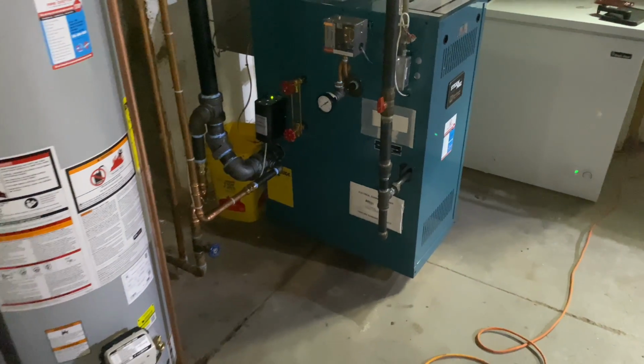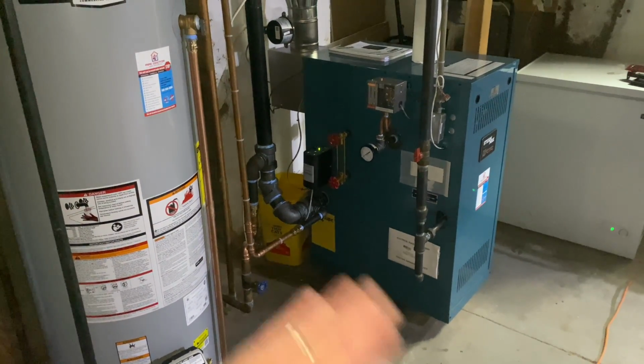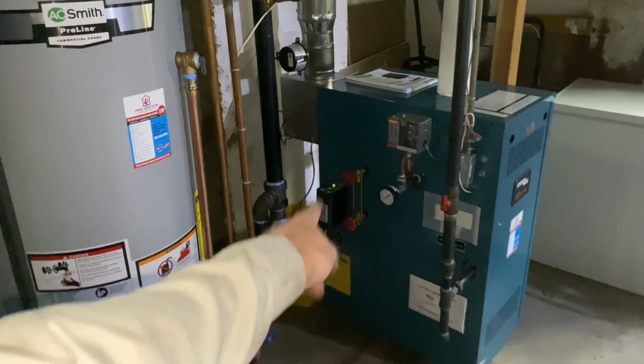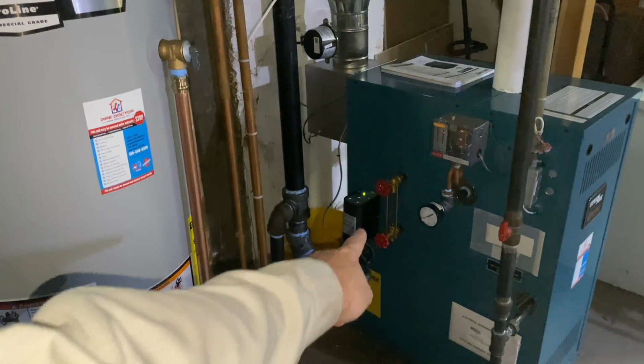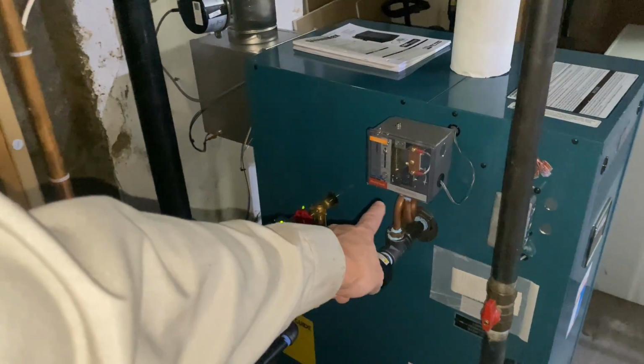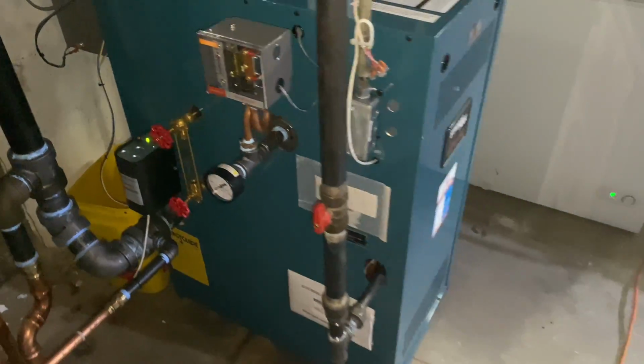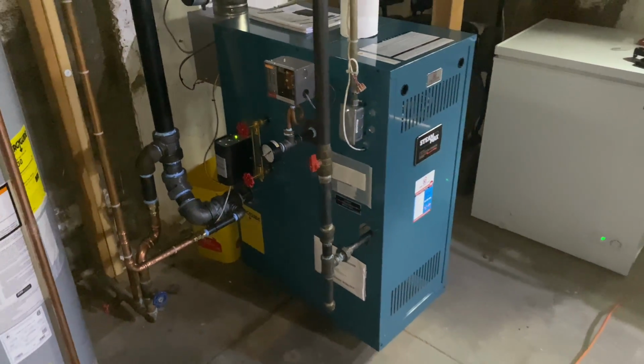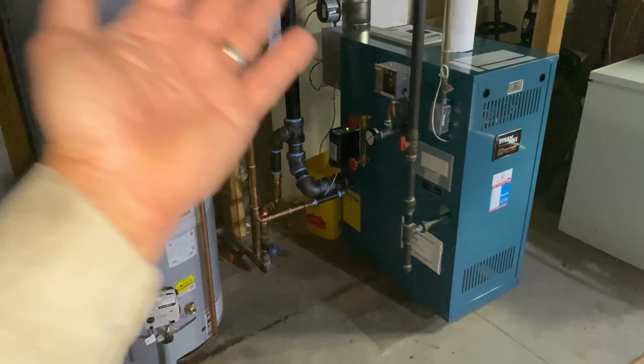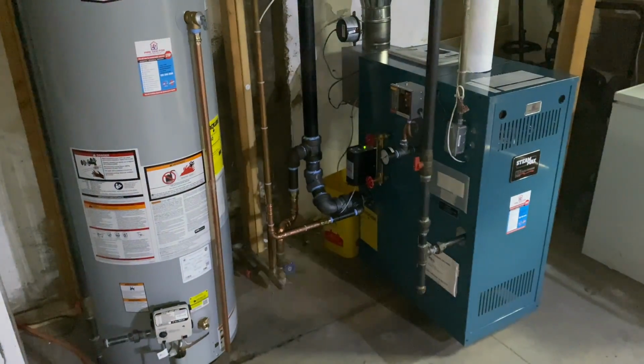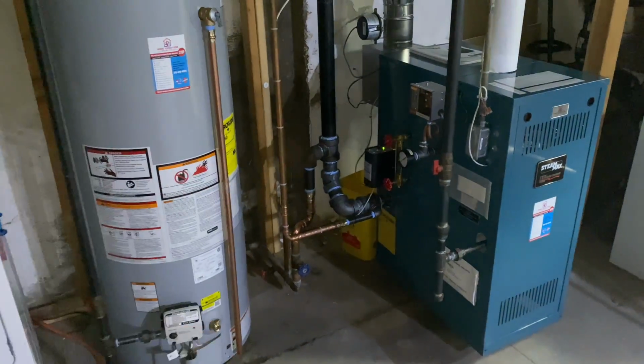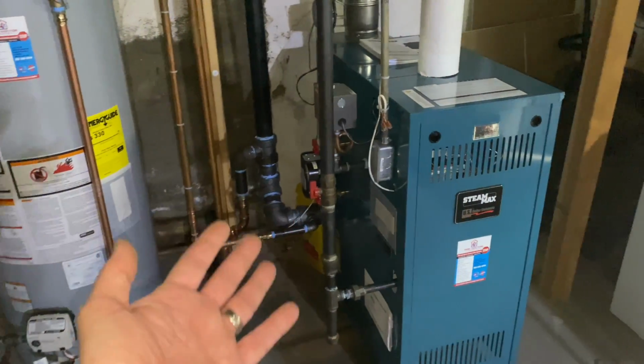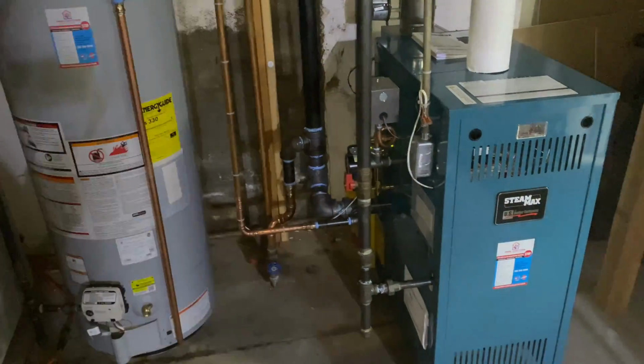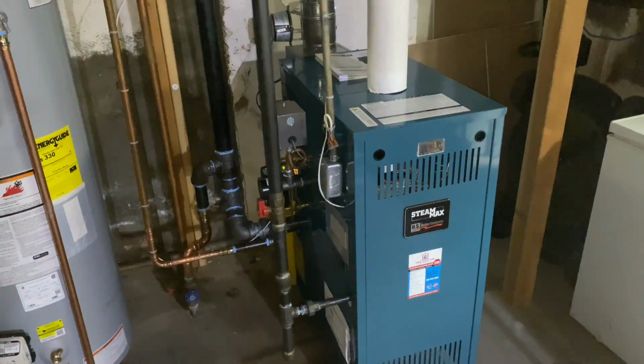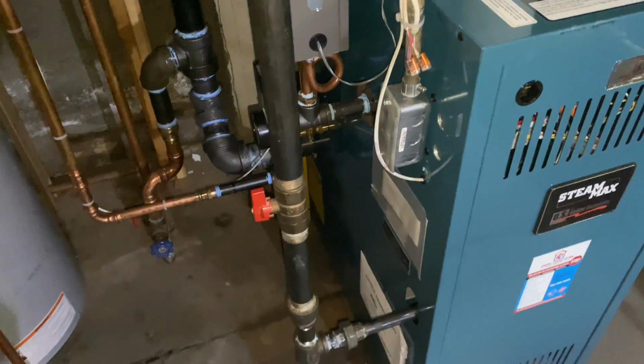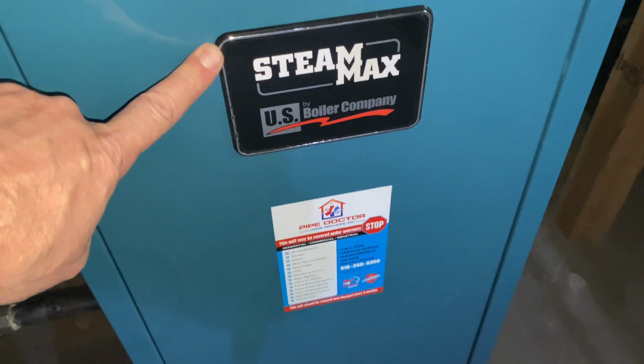What's really nice about the SteamMax by Burnham is it comes pre-trimmed. That means the low water cutoff is installed. Our sight glass is installed. Our pressuretrol, our pressure gauge, our pigtail, our electrical components are all pre-wired. Now, I get it. Sometimes you got to take all that stuff off to get into the basement, inside the house, like we did here as well, and like most of our SteamMax installations. But it does help us not have to worry about wiring the whole thing up when we're all done and we have that bird's nest of wire right here. Beautiful SteamMax by US Boiler.